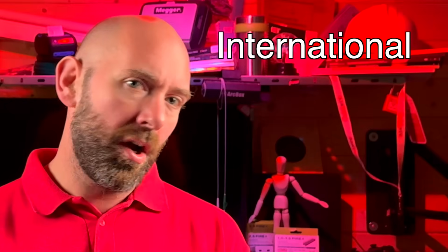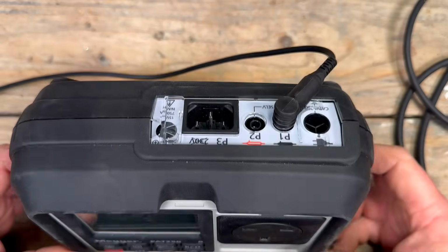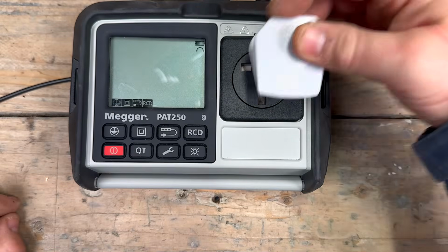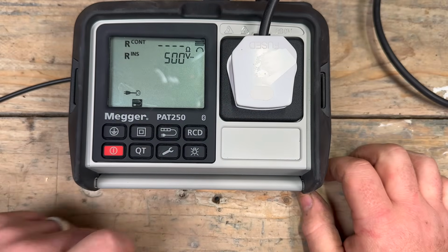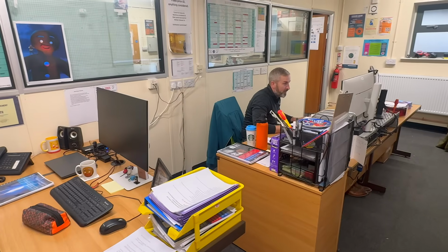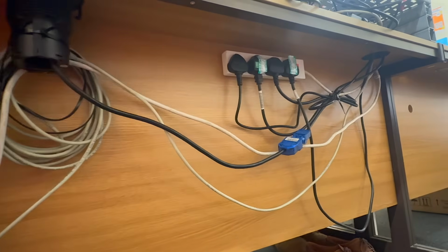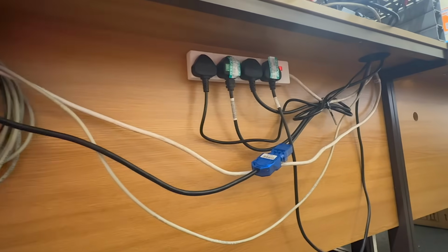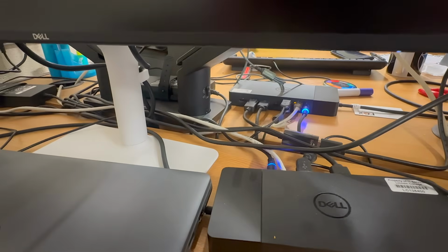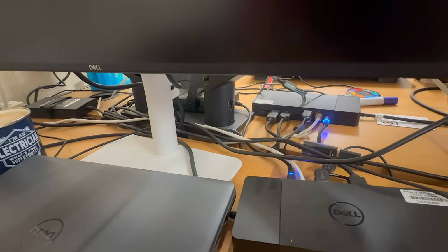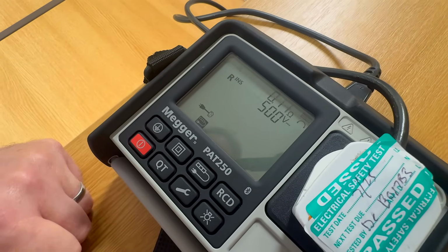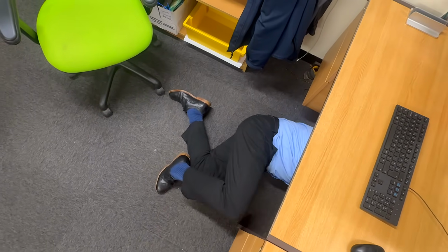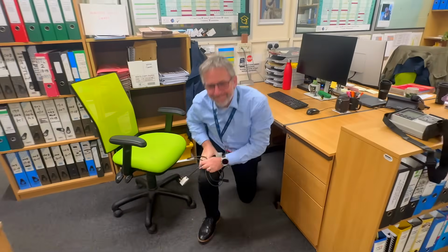Next up, we're going to test this IEC lead. And for this test, the PAT250 does all the work. At the back, you plug in the IEC lead and plug the plug into the tester. To test, we use the extension lead setting. IEC leads are very common in office environments, and sometimes it's easier to just unplug the IEC leads and test them in isolation. This reduces the risk of putting any dangerous voltages through electronic equipment, but confirms that the lead is in good condition and fused correctly. It can mean that you spend time under desks having to get hold of the leads, but it is one of the easiest of appliances that we can test.